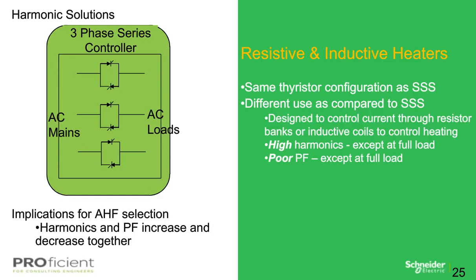So another type of three-phase controller is the inductive and resistive heaters. The intention of the heaters is to manage the load flow to maintain heating levels in the loads. These may operate at reduced load flows for long periods of time. Thus, the DPF and harmonics must be addressed. Same thyristor configuration as the SSS or the soft starter, but different when used as compared with the soft starter, as it's designed to control current through resistor banks and inductive coils to control heating. And typically what you see is high harmonics, except at full load, and very poor power factor, again, except at full load.